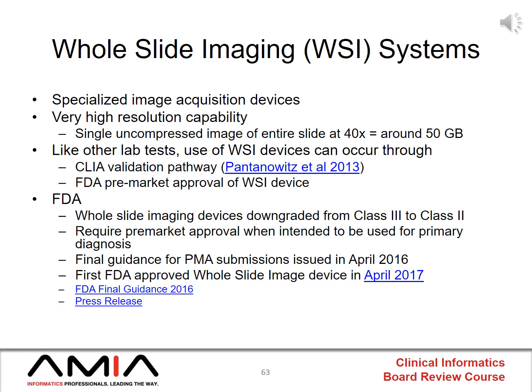The vast majority of telepathology practice requires the use of a whole slide imaging system. These systems are specialized image acquisition devices. They have extremely high resolution capability. As a result, a single uncompressed image of an entire slide at 40x resolution will render an image that's about 50 gigabytes in size.